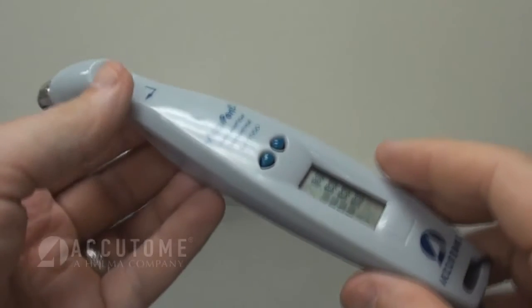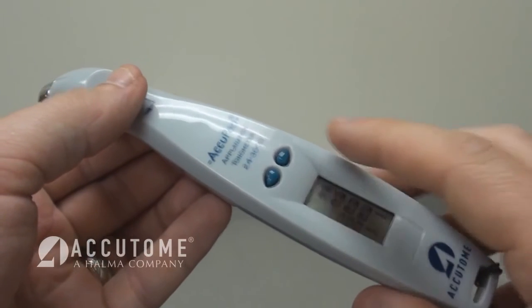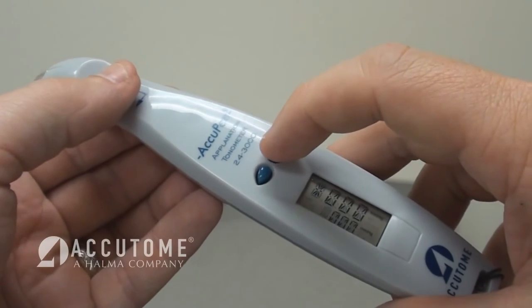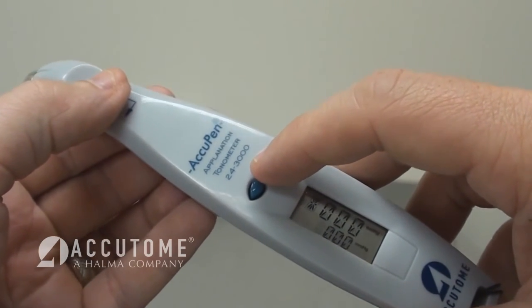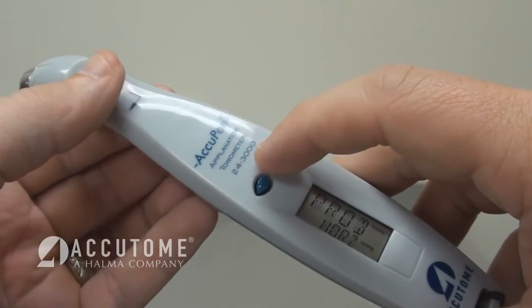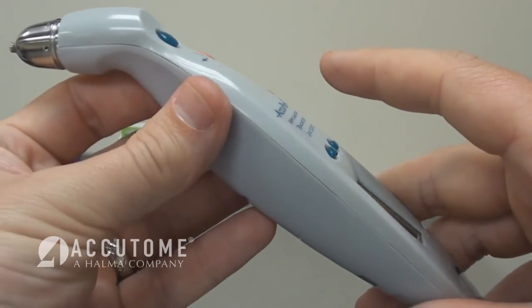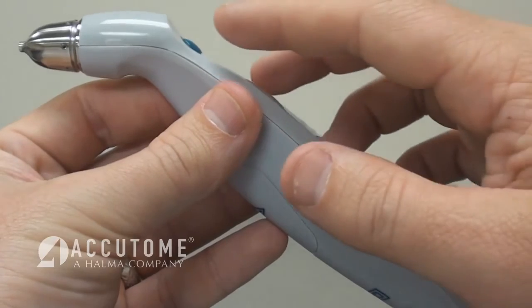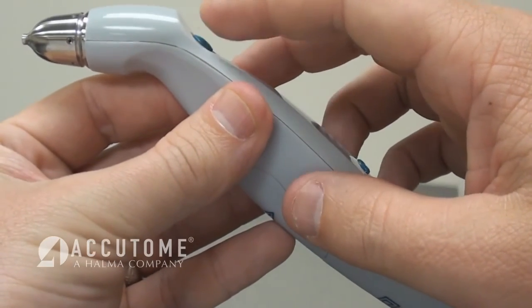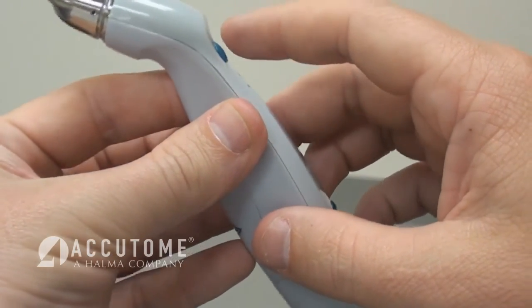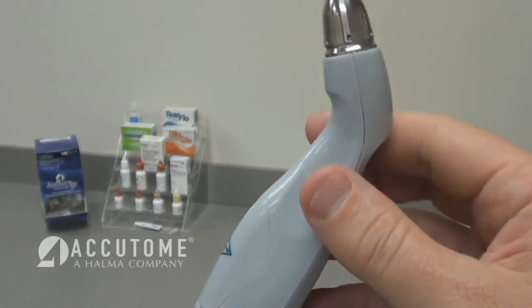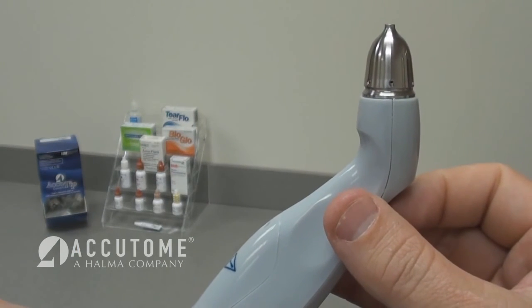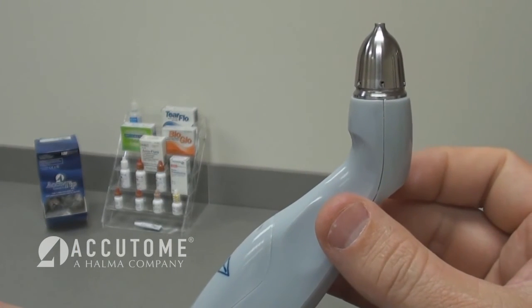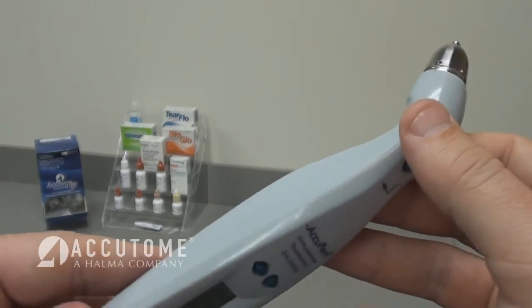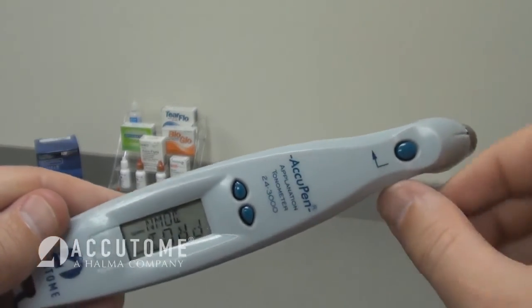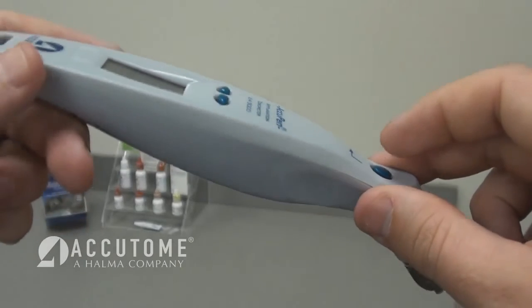When calibration is necessary, simply hold the up arrow and action buttons simultaneously for about 3 seconds until the prob horiz display screen appears. Hold the transducer horizontal to the floor and press the action button. The unit will chirp and display prob up. Hold the unit so that the transducer tip is pointed directly in the air and press the action button. The unit will then chirp and display prob down.